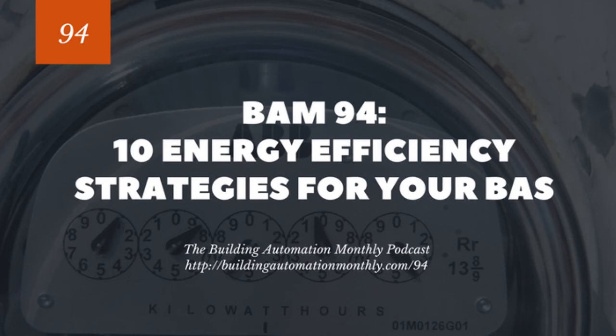Now, if we remember that essentially moisture, water, is our enemy when we're working with outdoor air, because if I have 80 degrees at 30% relative humidity, that has significantly less energy that needs to be removed, less BTUs, because remember, BTUs transfer from hot to cold. So when I'm cooling that air, I'm going to be taking those BTUs out of that air and transferring them into the chilled water return. And that BTU is then, either through an air-cooled chiller or through a condenser, through a cooling tower, exhausted back to the atmosphere.